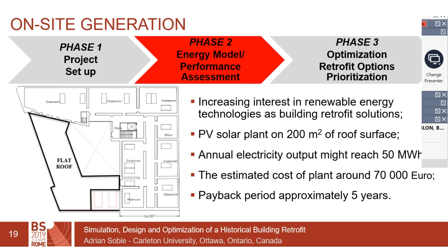We also wanted to maximize on-site power generation. We noticed there was a flat area on the building not visible from street level, and we recommended installing solar panels there — producing energy without significantly impacting viewplanes from the street or exterior appearance. The analysis found it would cost about 70,000 euros, with a payback period of approximately five years.